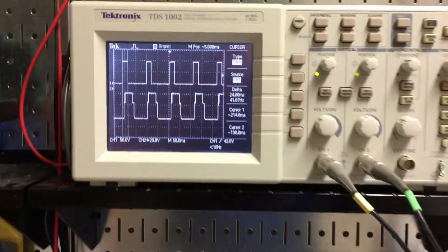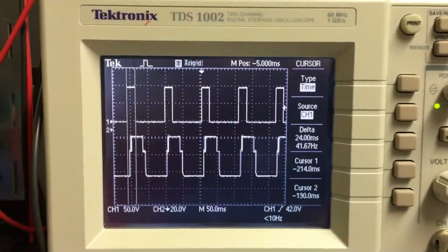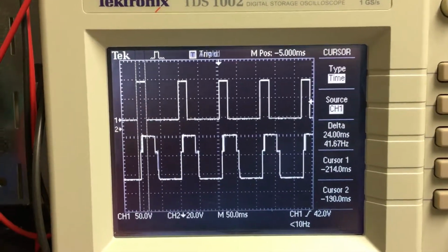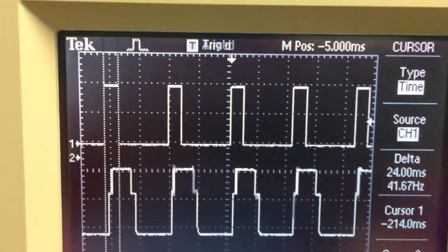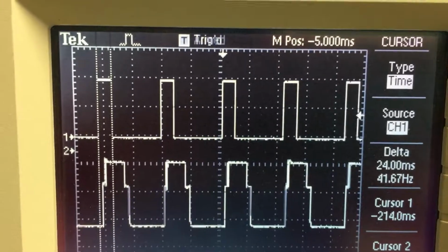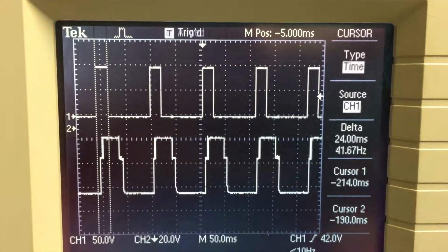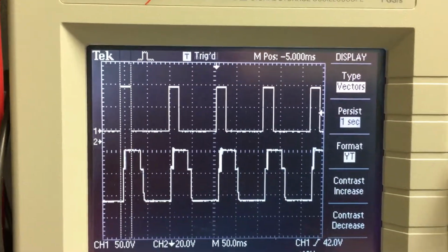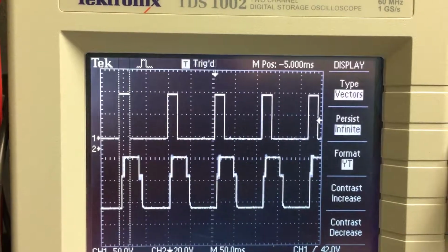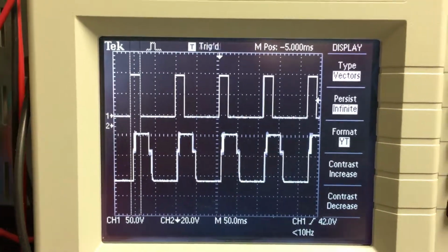Okay, this is a follow-up on cutting fiber over transfer trip. So I've increased the frequency of the trips to something around 10 Hertz, and I'm transmitting a trip here that has a duration of 24 milliseconds. That's what I measure right there. And I'm gonna make the trace persistent. This way, if something happens in between, we should be able to capture it.